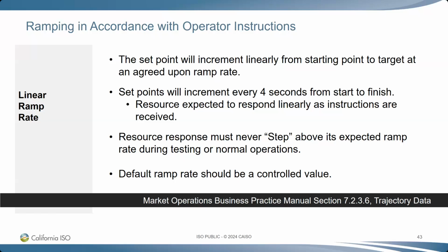An example of a resource went up 250 megawatts instantaneously. But if you look at San Francisco, their average load can be between 300 and 600 megawatts. So that change can be quite significant. Multiply that across the whole system, it can have those impacts, and then the system has to rebalance itself out. So not stepping above, making sure you have that linear ramp, is going to help the system balance and not have to either drop or pick up more megawatts to compensate.